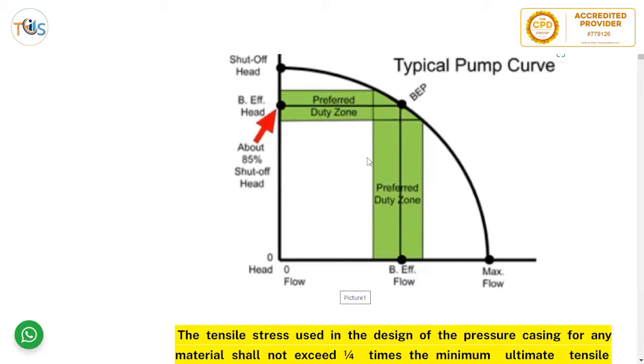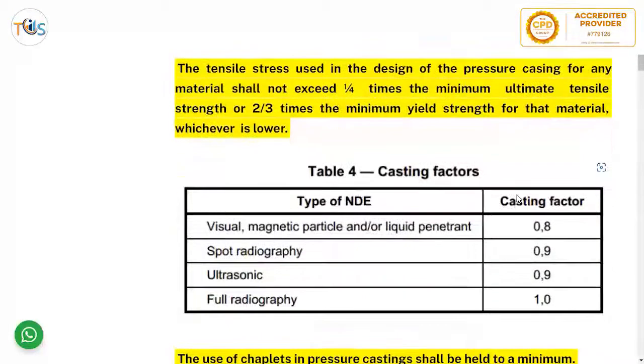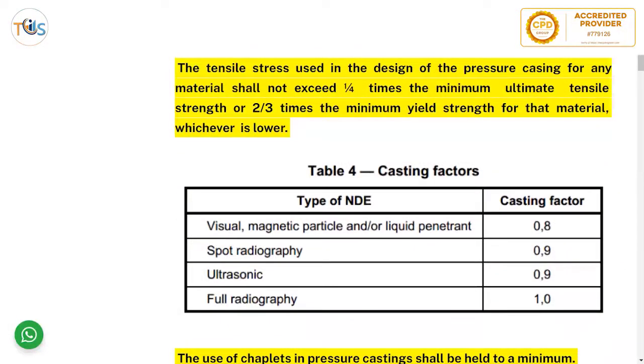The tensile stress used in the design of the pressure casing for any material shall not exceed one-quarter of the ultimate tensile strength or two-thirds of the yield strength of that material, whichever is lower. This gives a safety factor of roughly 3.5 to 4 times. This is consistent with ASME Section II materials and ASME Section VIII, which also use allowable stress of approximately one-quarter of the minimum ultimate tensile strength.